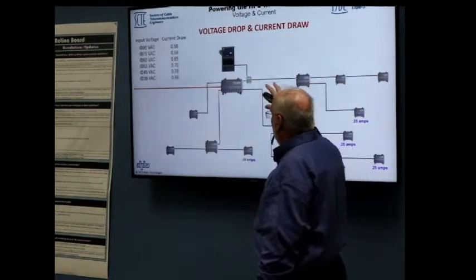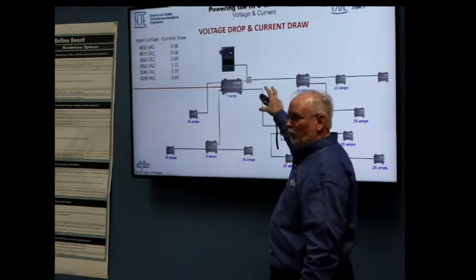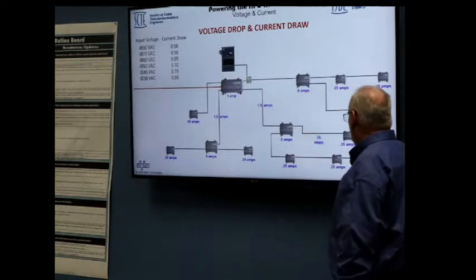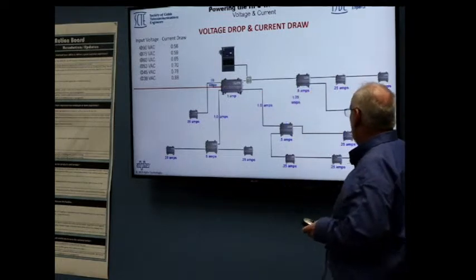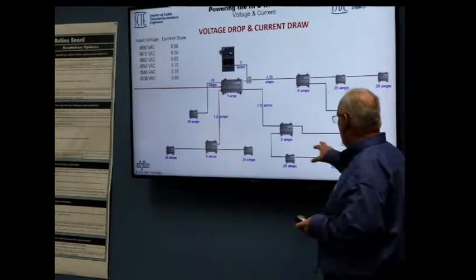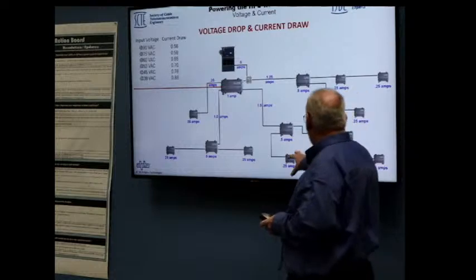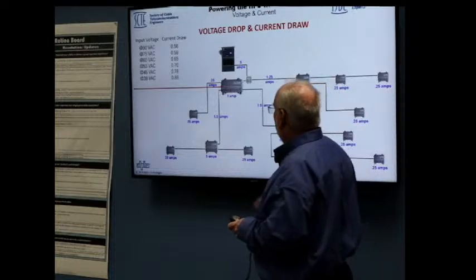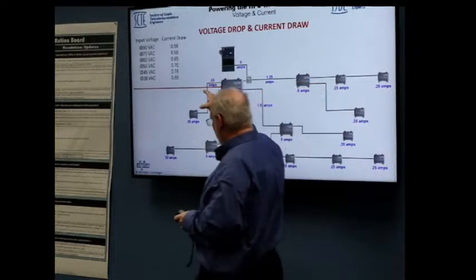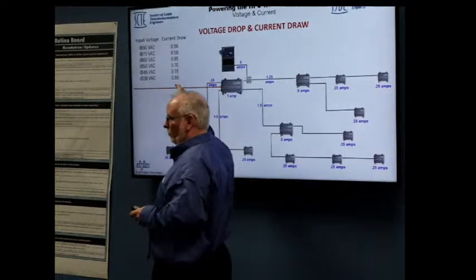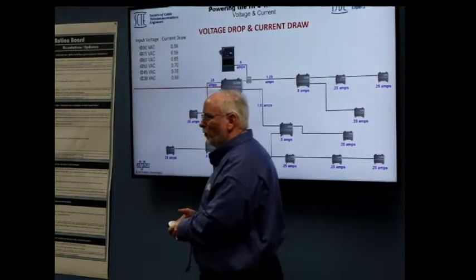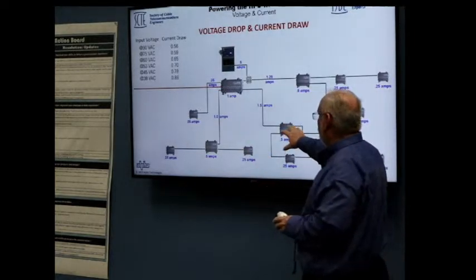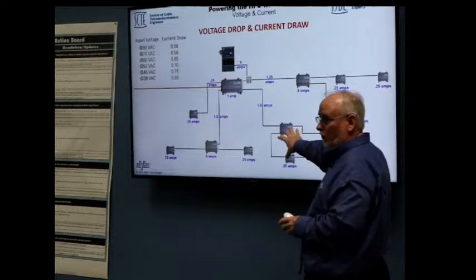So, the HFC plant, believe it or not, has a lot of voltage loss throughout the system. When you start looking at where current is traveling, it's not just the 0.25 or 5 amps, it's what it all sums up to, right? And there's resistance on each one of these lines. There's also a thing over here. This is a voltage versus current chart of a switching power supply. Remember I told you that one image was old school with the transformer in the front of it? So these devices will run from 90 volts down to about 45 volts.